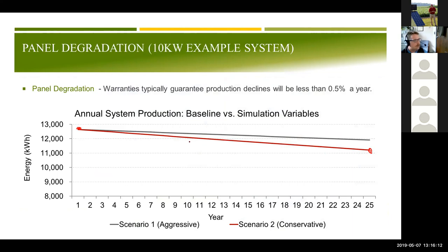And if the degradation were ever to fall below this line, they would then warranty out the solar panels. So it's going to stay above this line of where they will provide 80% of what they were when new, at 25 years old. Now, does that mean they won't run past that? Sure they will. As long as other damages haven't taken place, they'll run beyond that 25 years. It's just that degradation is going to be below 80%, which is out of the warranty time for the solar panels.